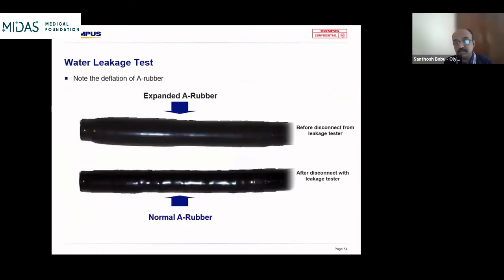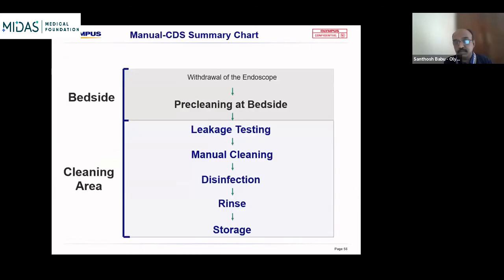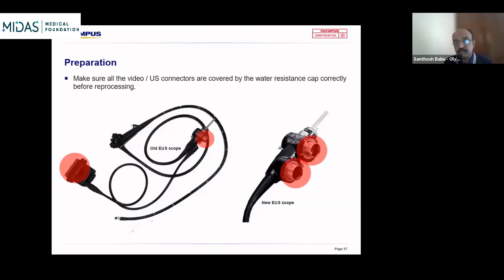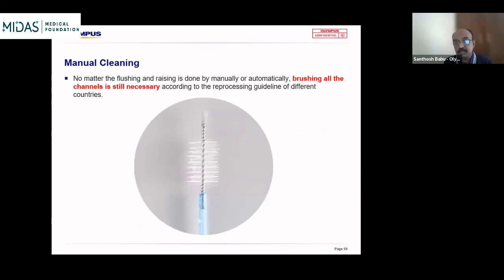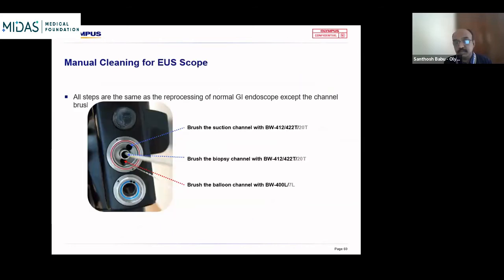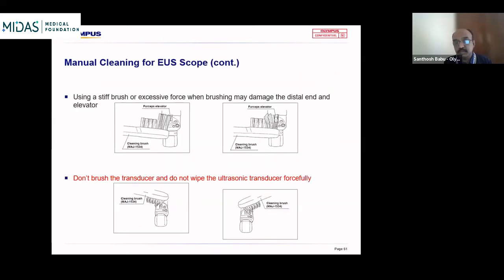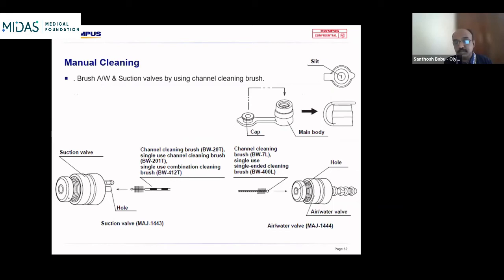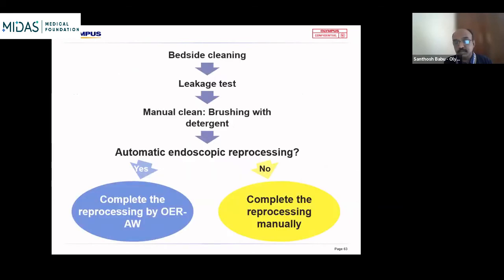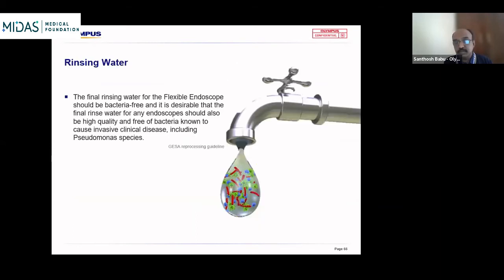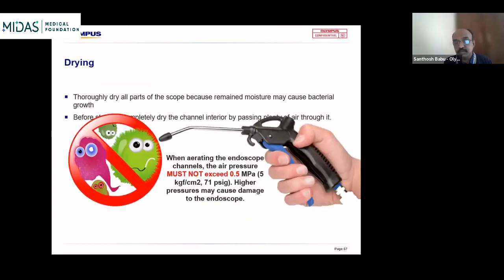There are a few steps that you need to know. This is the actual sequence, from pre-cleaning to leak test, manual cleaning, disinfection, rinsing, and storage. Even if you have an AER installed, brushing is very crucial. Brush the channels prior to putting them into the washer. Be gentle on the distal end, especially on the transducer part. After cleaning and brushing, you decide whether to put it in an AER or continue the process. Rinsing is done at the end of the disinfection cycle.